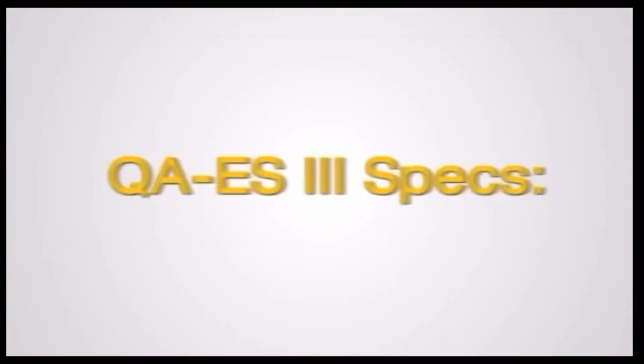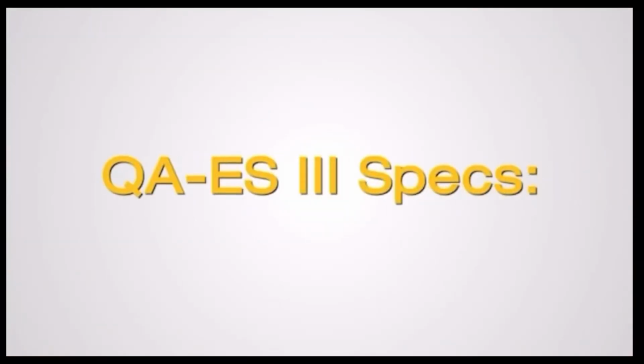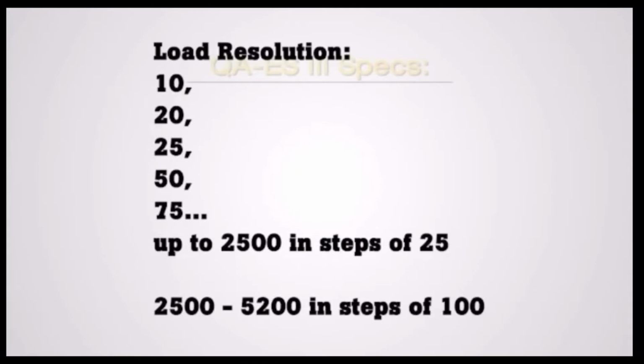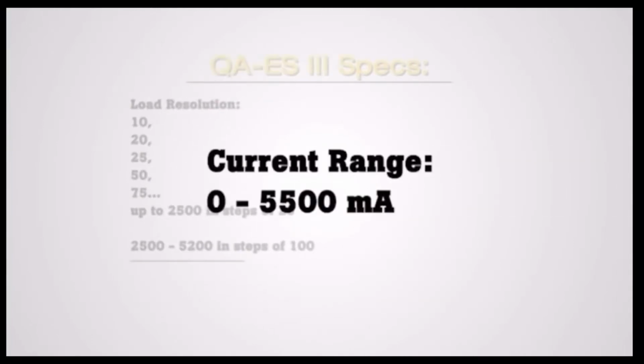With state-of-the-art technology, the QA-ES3 provides exceptional accuracy and range of measurement. Its wide range of loads allows users to test the breadth of electrosurgical generators. Notably, the QA-ES3 has a 20-ohm load to support Valleylab electrosurgical units, including the Force Triad. The QA-ES3 also has double the RMS current range of its predecessor. It can measure current from 0 to 5500 milliamps.